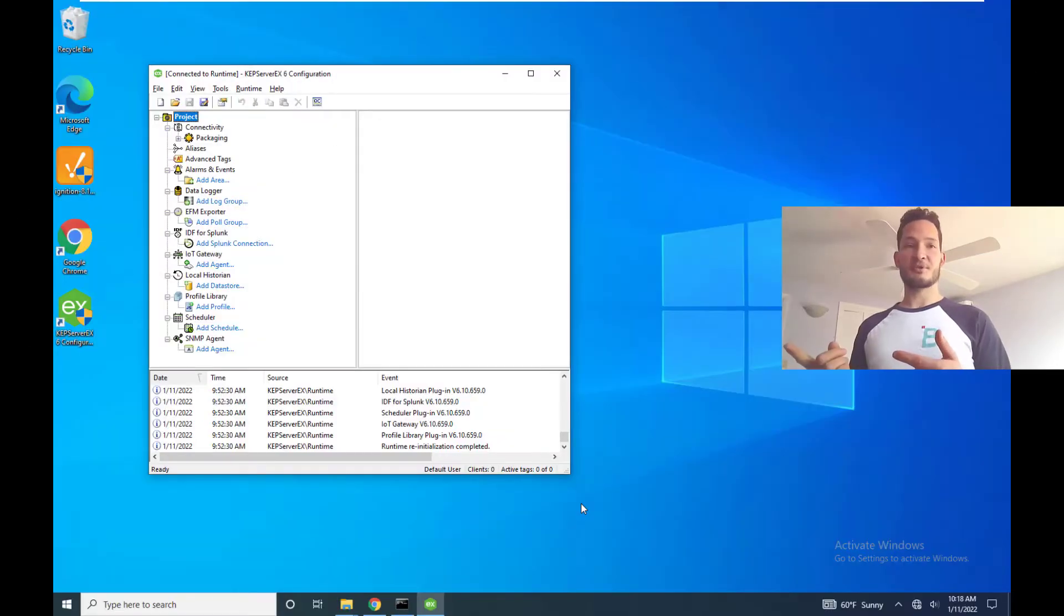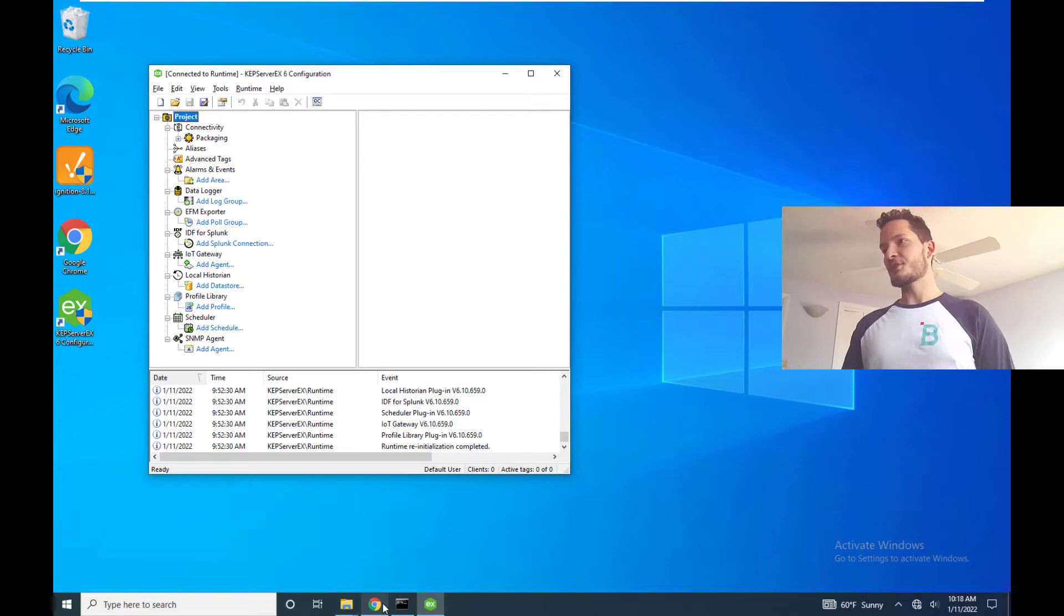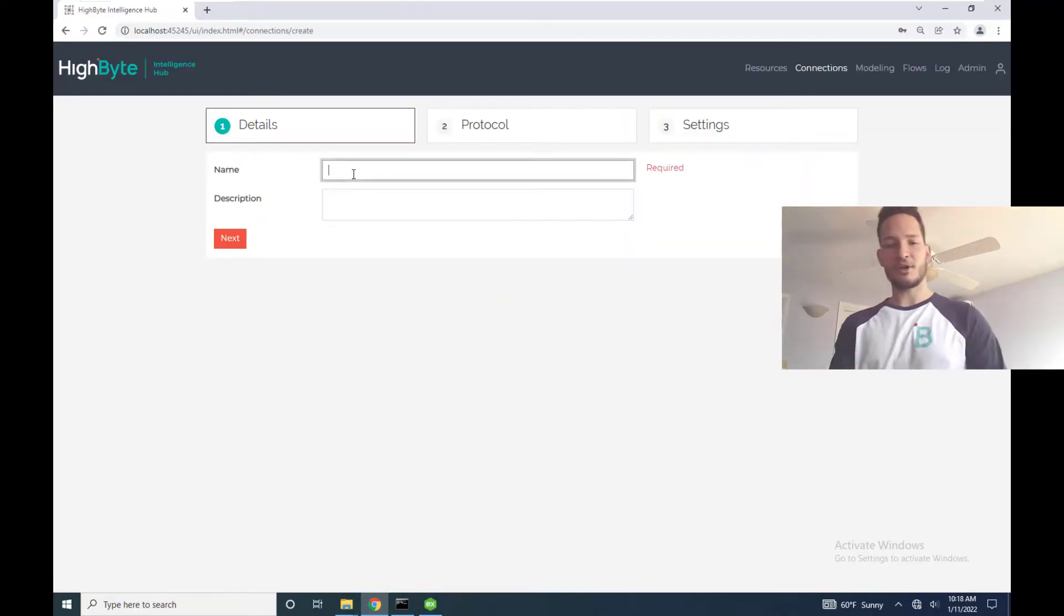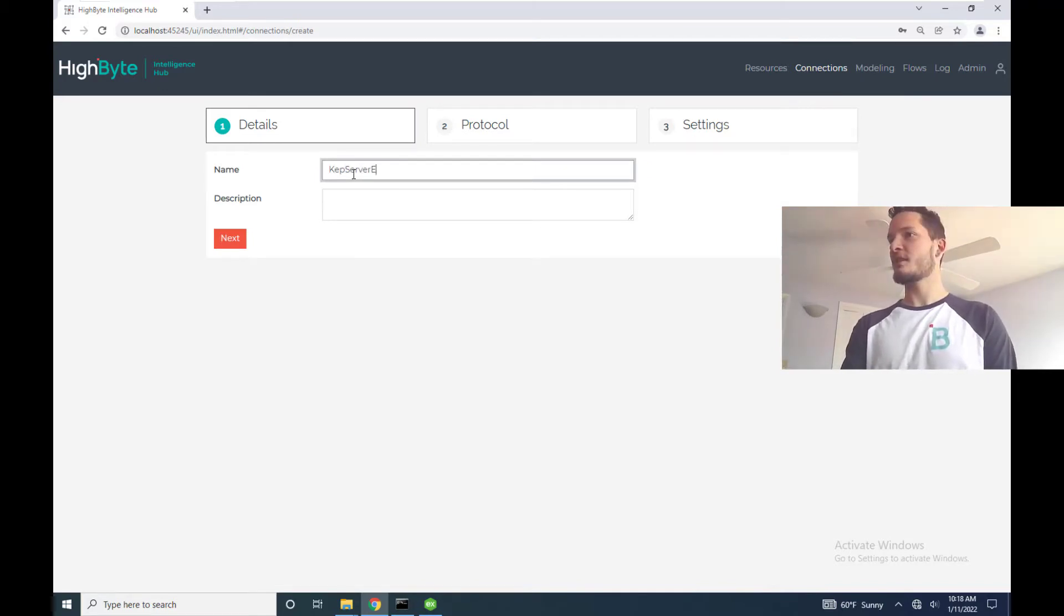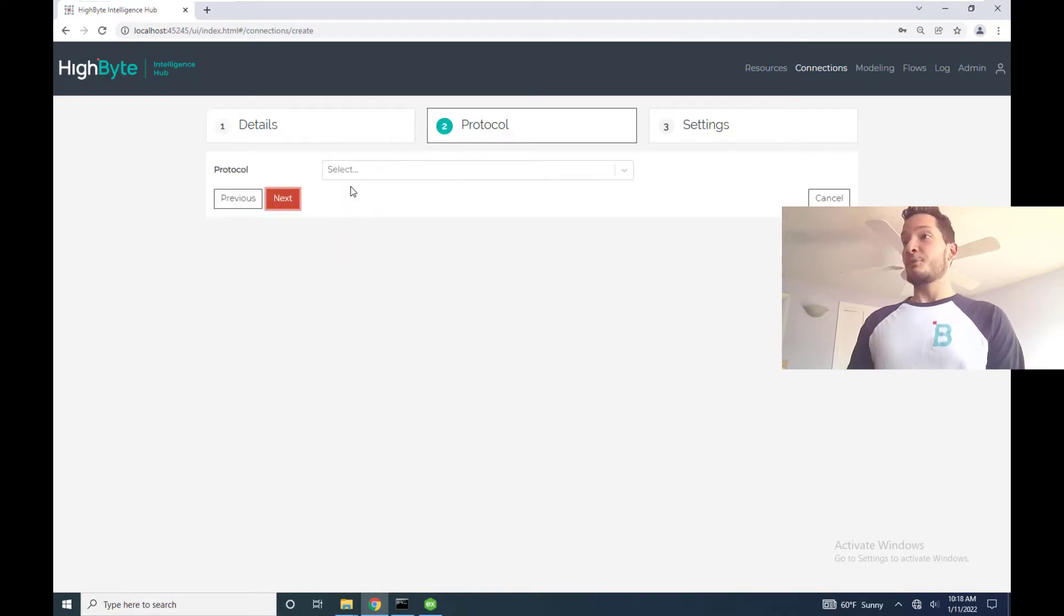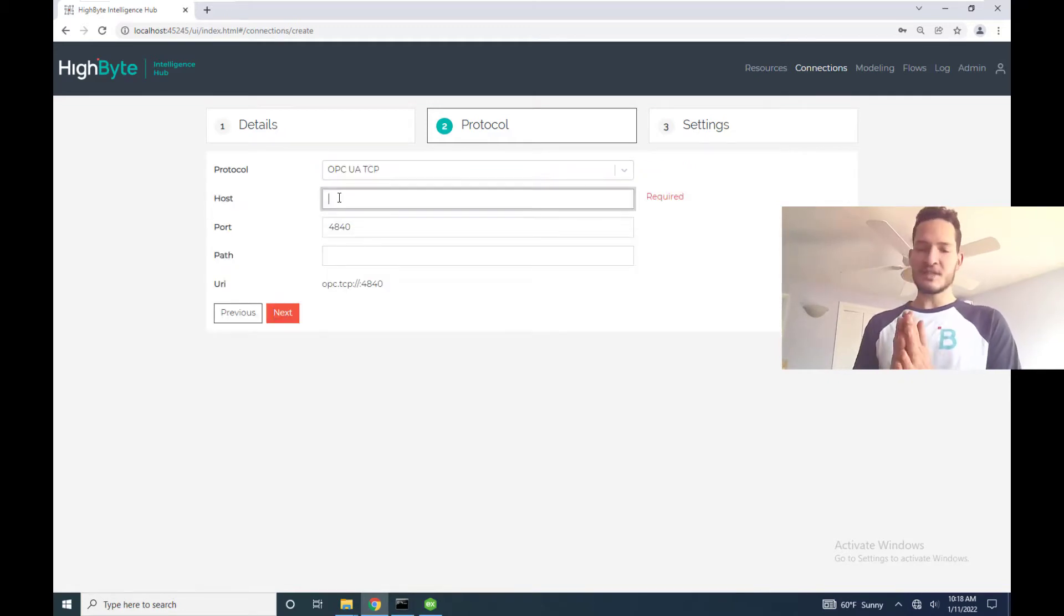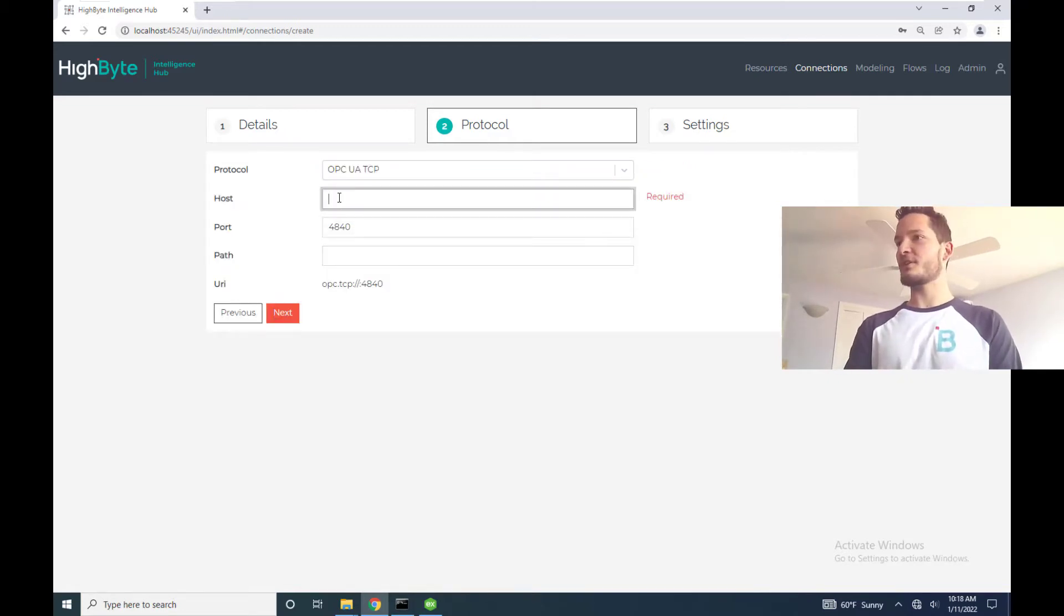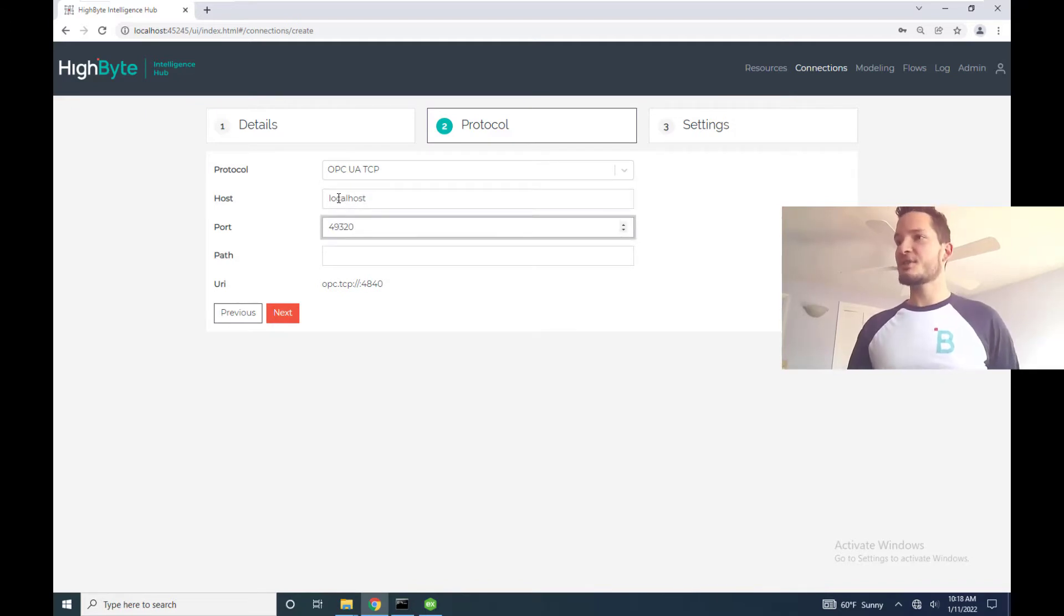So the first step in connecting to my Kepware server EX is going to be to create that connection within HiByte. So I'm going to go to my HiByte Intelligence Hub on the connections page and then create a connection. I'm going to call it Kepware server EX and describe it as my OPC server. The protocol as you may have guessed is going to be OPC UA over TCP and then for these settings because it's locally installed I'm going to use localhost and then default port for Kepware which is 49320.